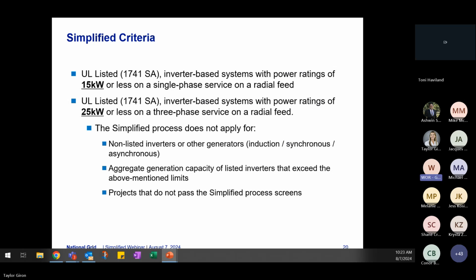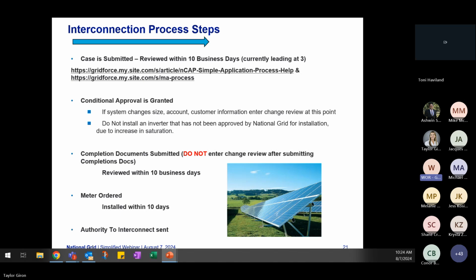So the simplified criteria consist of UL 1741 SB listed inverter-based systems with power ratings of 15 kW or less on a single-phase service, or UL 1741 SB listed inverter-based systems with power ratings of 25 kW or less on a three-phase service. The simplified process does not apply for non-listed inverters or generators, aggregate generation capacity of listed inverters that exceeds the above-mentioned limits, or projects that do not pass the simplified process screens. Next slide, please.